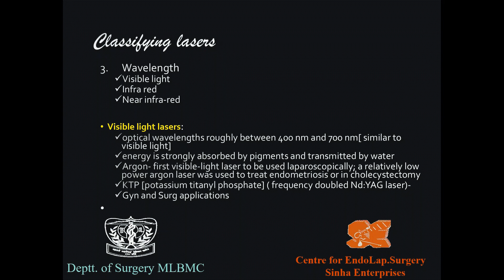Classification by wavelength: visible light lasers have optical wavelengths roughly 400–700 nm; energy is strongly absorbed by pigments and can be transmitted through water. Argon was the first visible light laser used laparoscopically, for example to treat endometriosis. The KTP (potassium titanyl phosphate) laser is a frequency-doubled Nd:YAG laser — doubling the frequency, halving the wavelength — commonly used in gynecological applications.